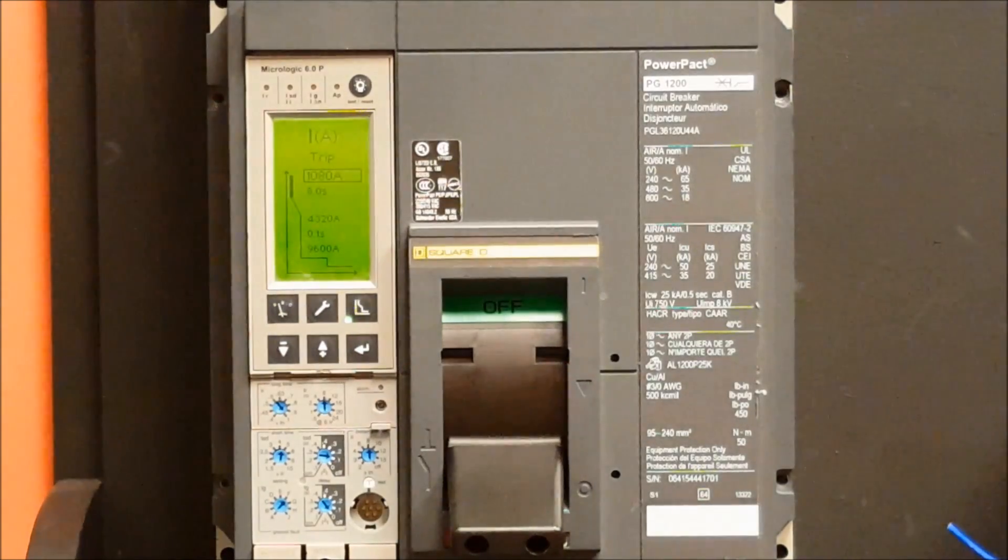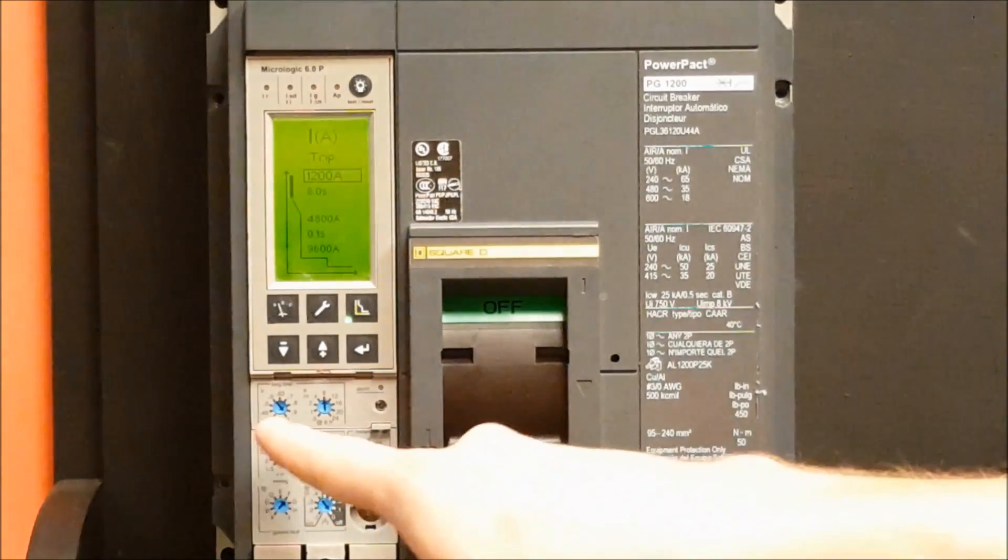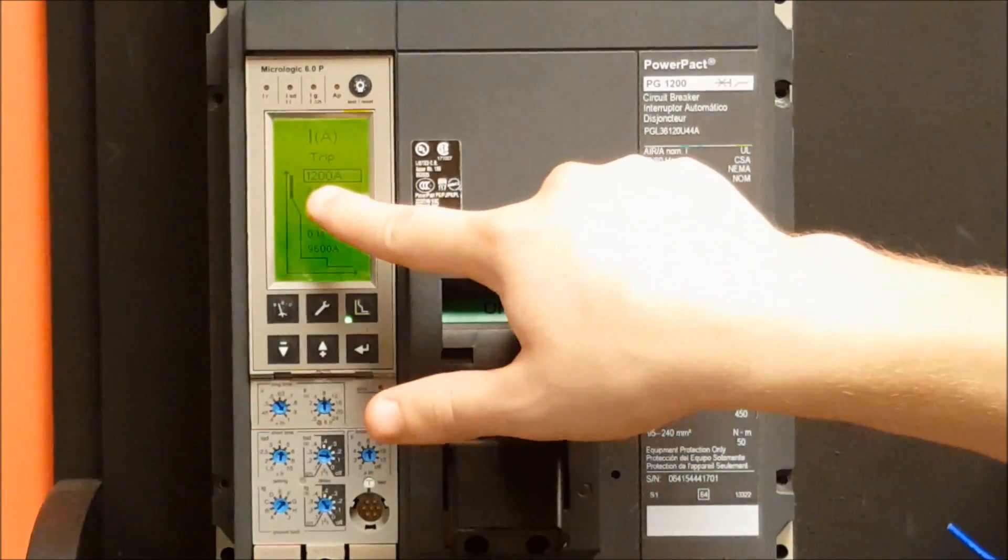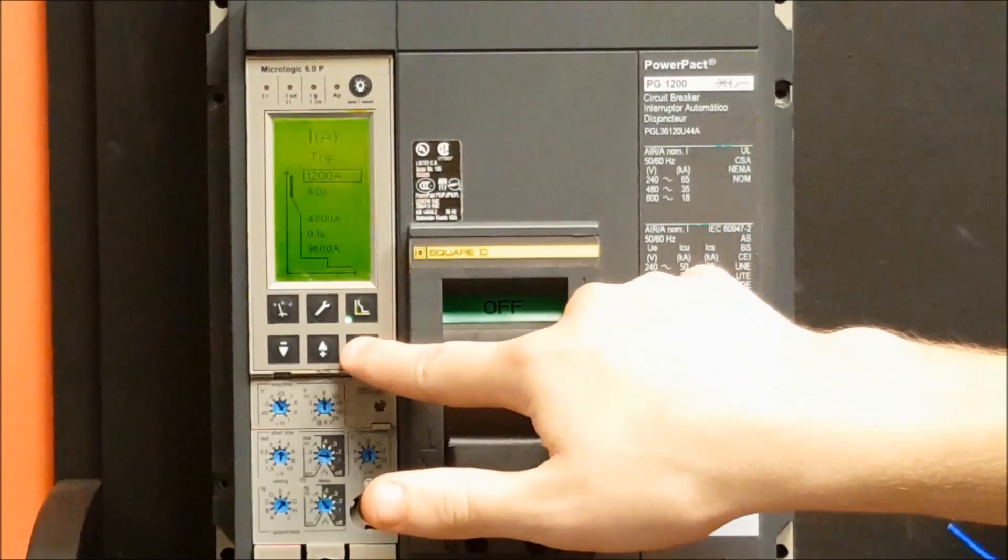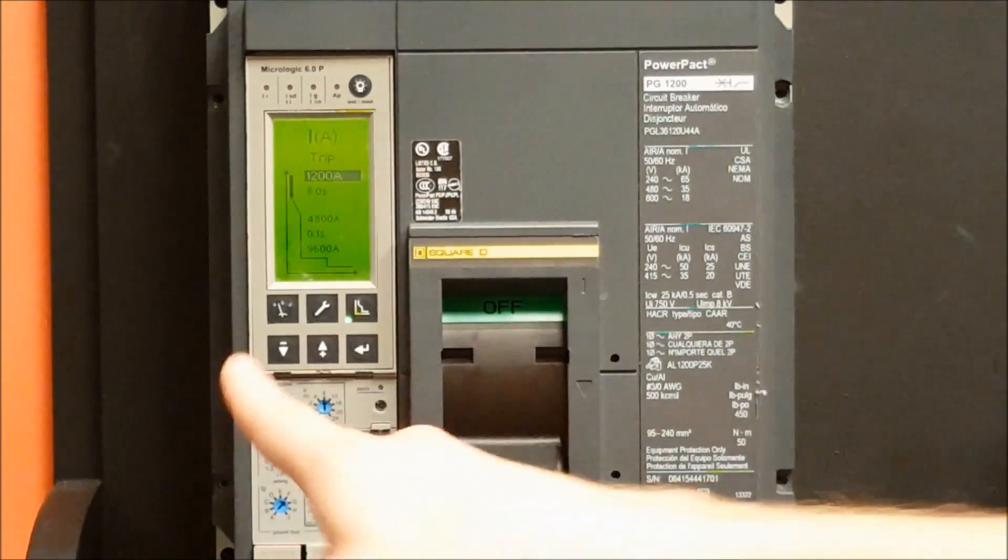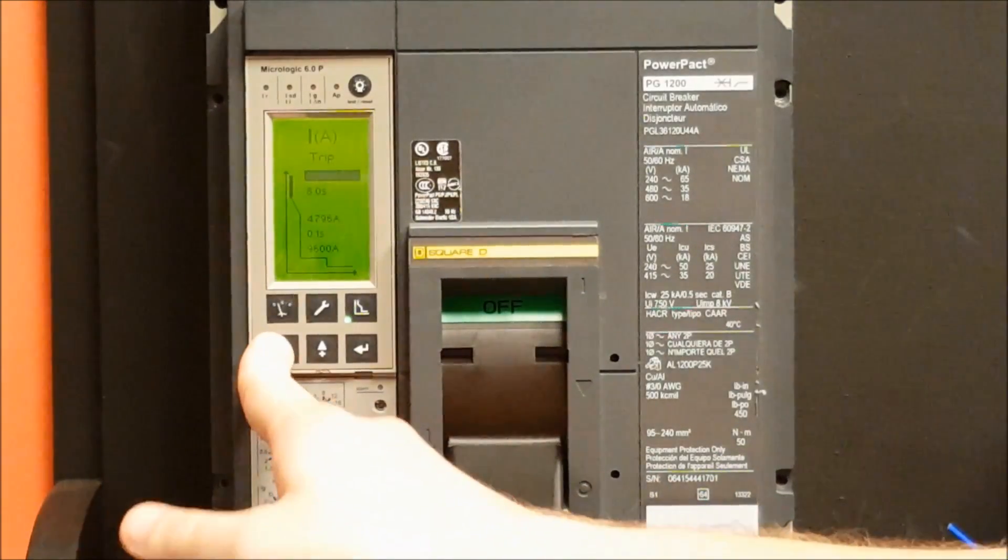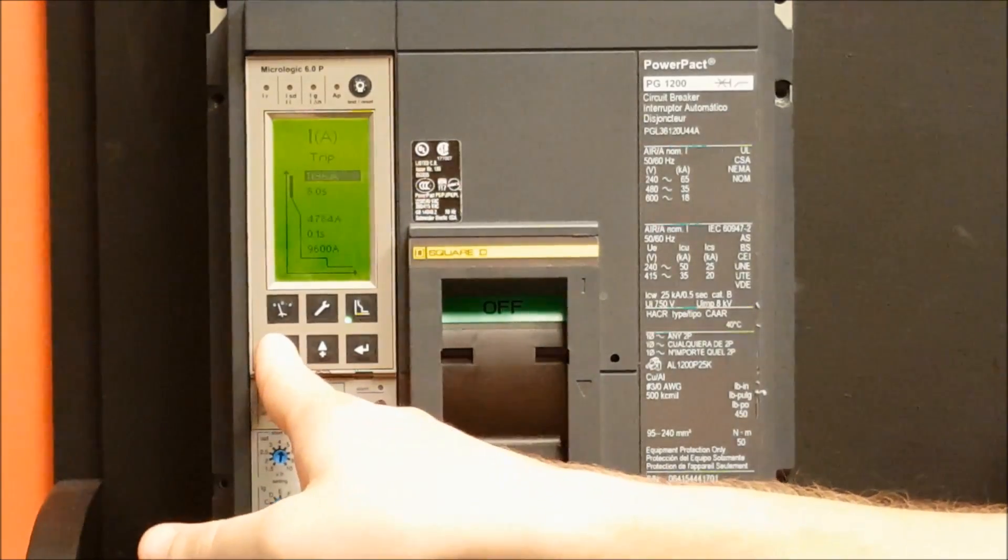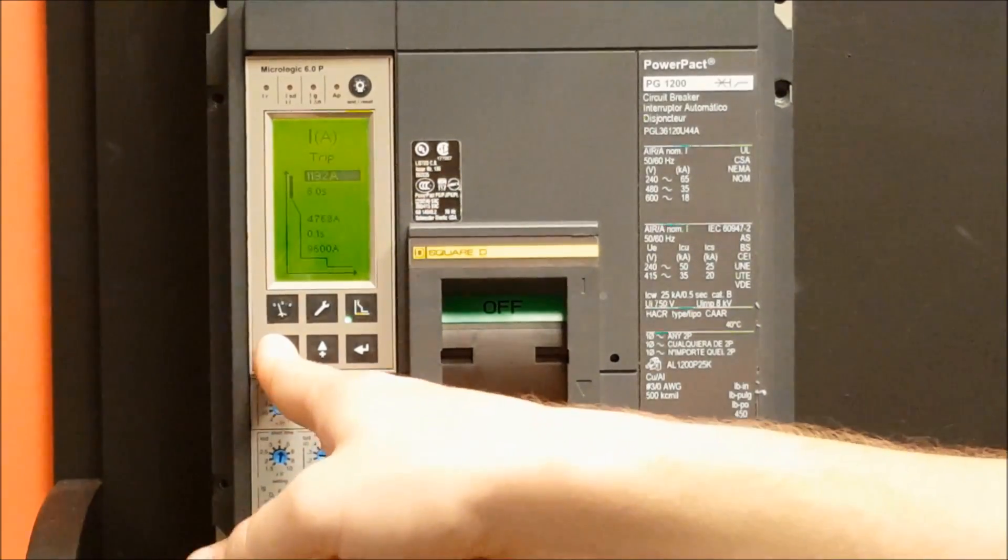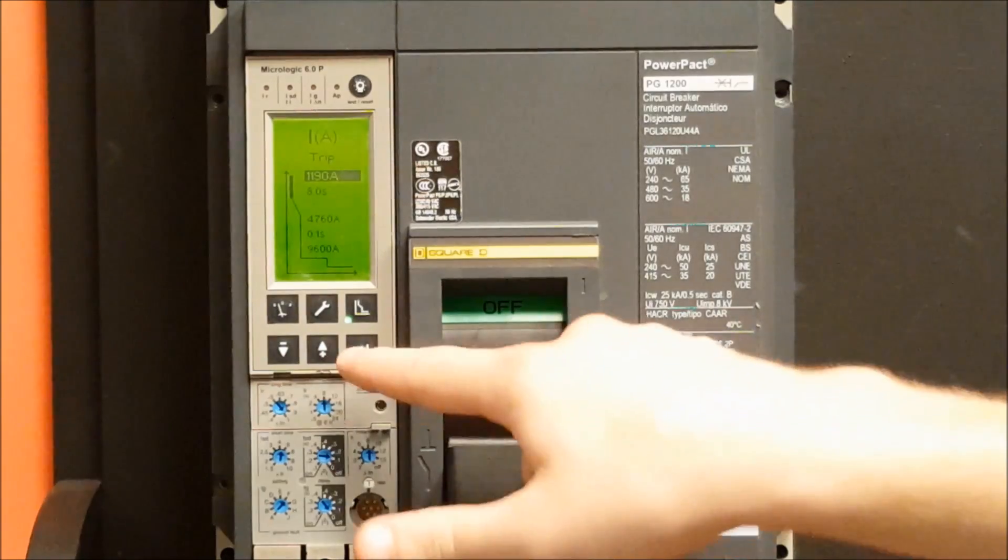For example, if you wanted to change it to 1190, we would get the dial to 0.1 where it shows 1200 amps. Then you hit the select button which highlights it. Then you can use the up and down arrows to change it to 1 amp increments. In this case, we would go to 1190, hit enter to save it.